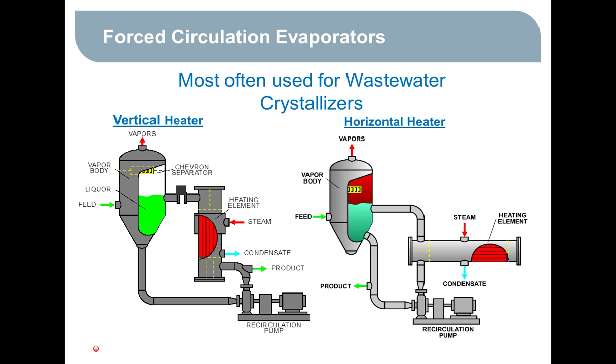And this is important because that vapor body, that flashing action at the inlet to the vapor body, causes the brine to become supersaturated, and that means that it's holding more solids than it can, so crystallization starts to occur. And the idea is that the volume of liquid in the vapor body has a sufficient residence time to relieve all of the supersaturation and grow the crystals in the tank. So by the time the brine comes back to the heater, all of the supersaturation has been relieved. So we don't get crystallization occurring in the heater itself, because that could result in the crystals adhering to the heat transfer surface. So this is a typical forced circulation type evaporator.